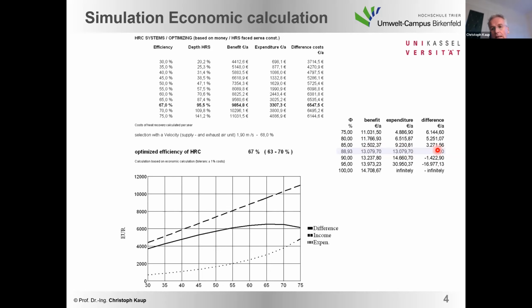So a too big heat exchanger will produce losses, just like a too small heat exchanger will not reach the optimum. And here in that example, you have a clear optimum under these framework conditions, prices, operating time, etc. In that example, at 67%. So here you have a maximum, if you play with the depth of the heat exchanger, of roughly 6,500 euros. That's one possibility to optimize your heat exchanger.